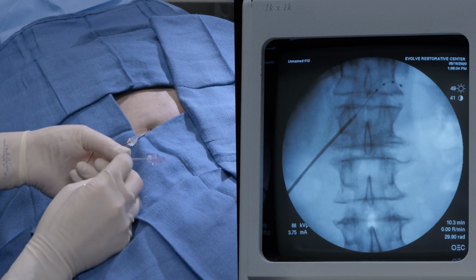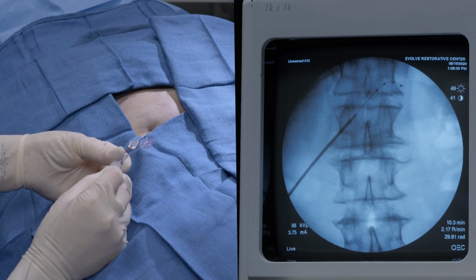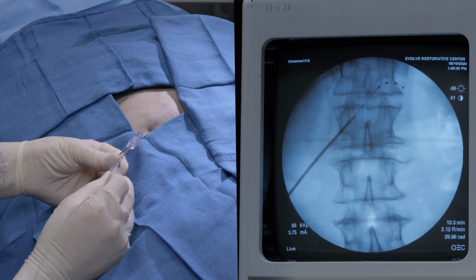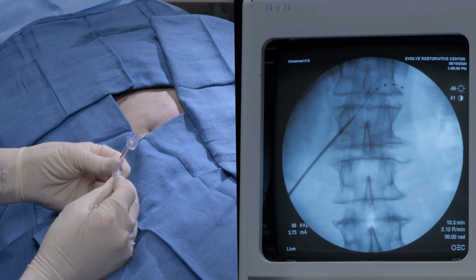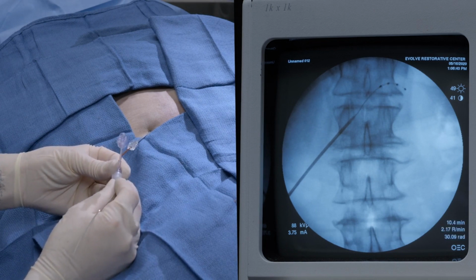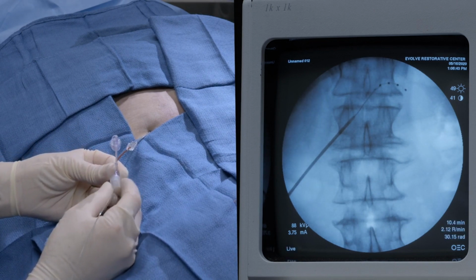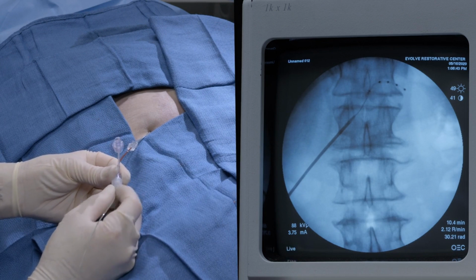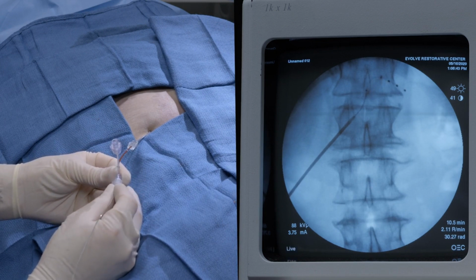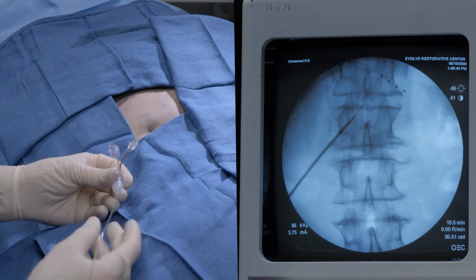So you're going to unlock now the end of the hub. And what you're going to do is begin to retract the sheath and advance the lead like a Seldinger technique, so that you can move the sheath back into or near the hub of the needle. Now, the thing you have to be aware of is that the most important step that's happening is right now. This is the locking mechanism.